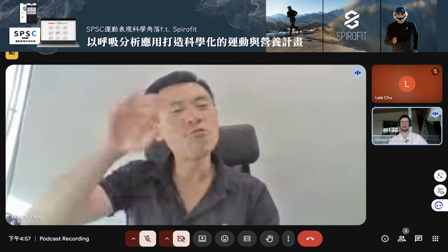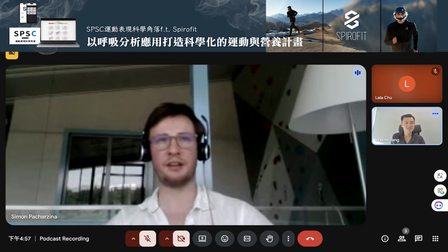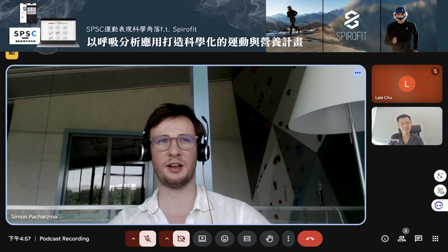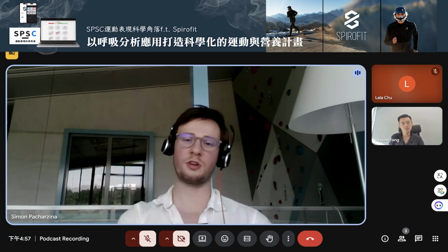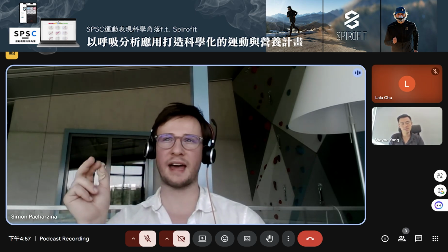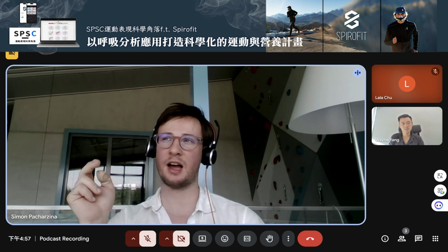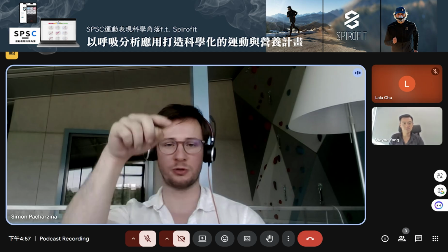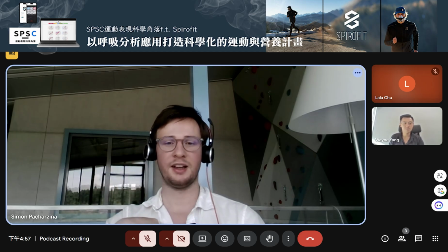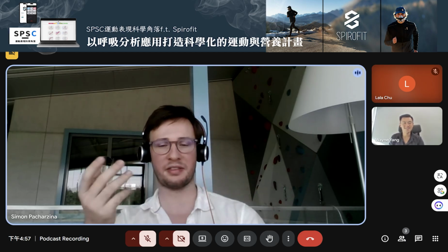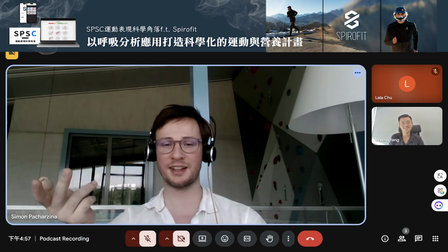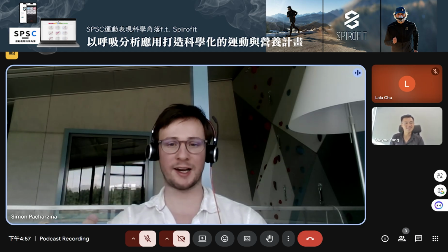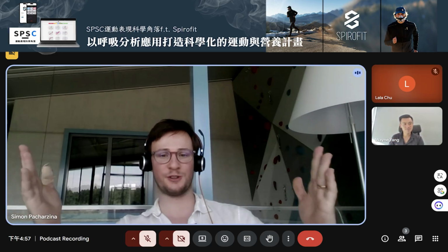Okay. And when you see outliers, do you take them out? Yeah, they are filtered. We have a moving average filter, and we have a median filter as well. Most of the outliers are falsely detected breaths. If you have a very small breath that doesn't contain any gases, you can be certain it's an outlier and it doesn't influence the measurement overall.